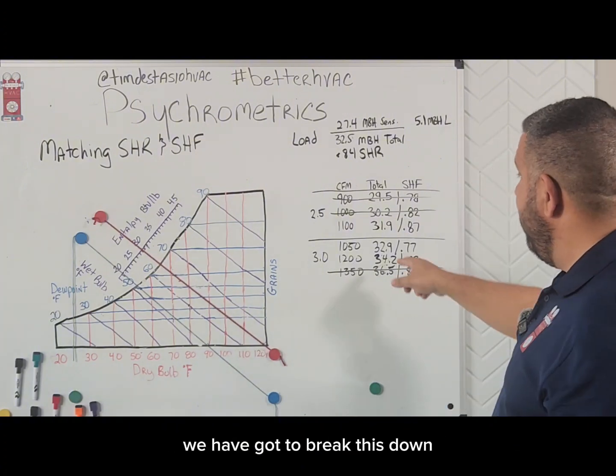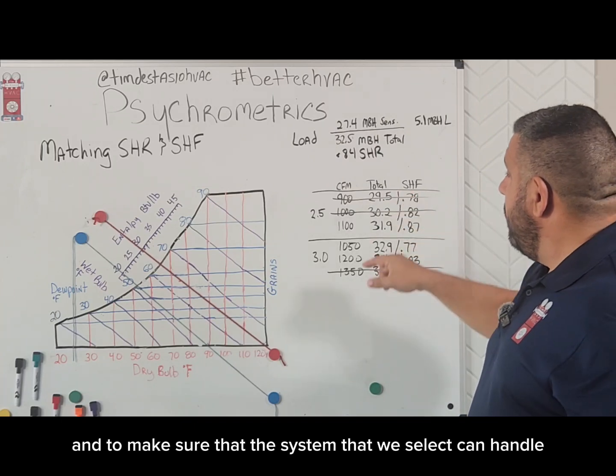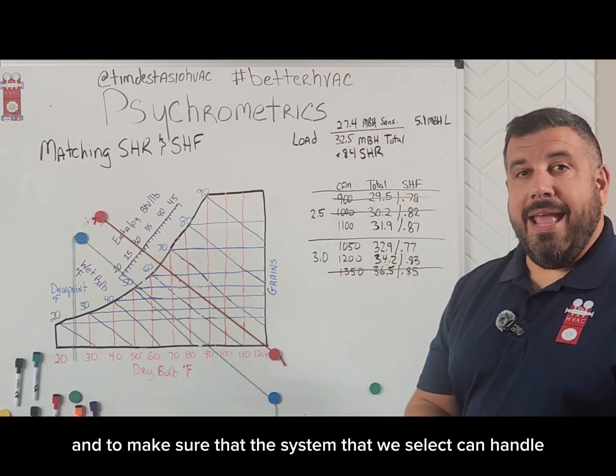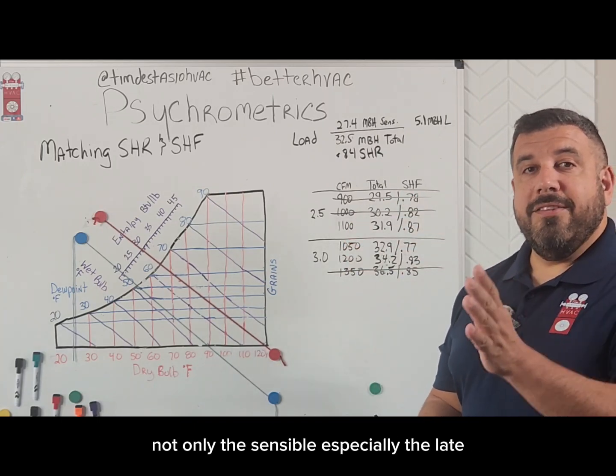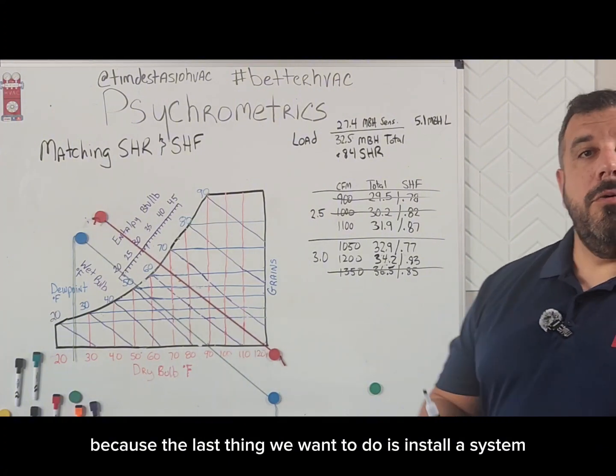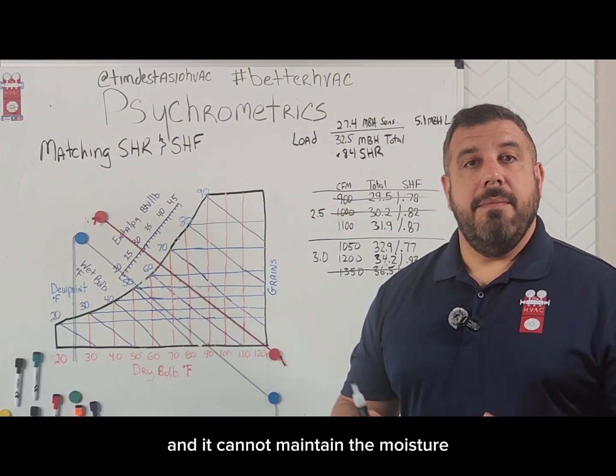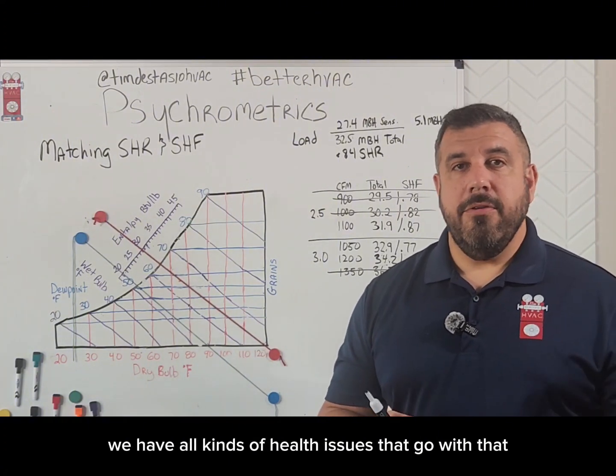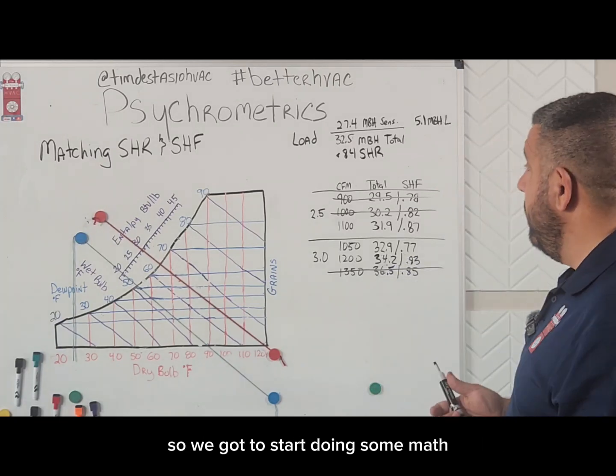We have got to break this down to make sure that the system that we select can handle not only the sensible, but especially the latent, because the last thing we want to do is install a system and it cannot maintain the moisture, and we have all kinds of health issues that go with that. So we've got to start doing some math.